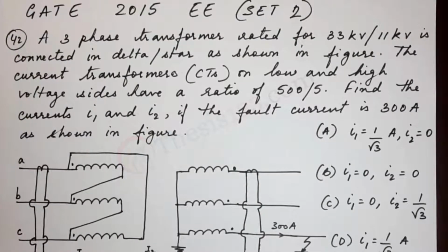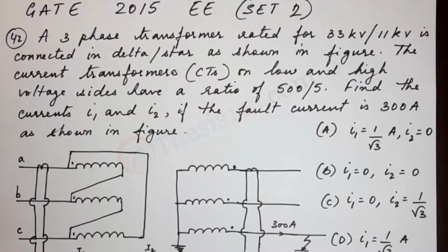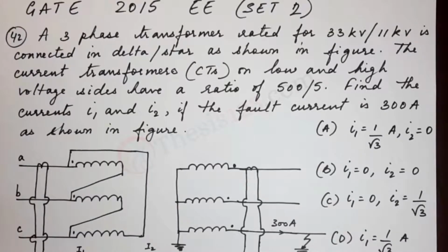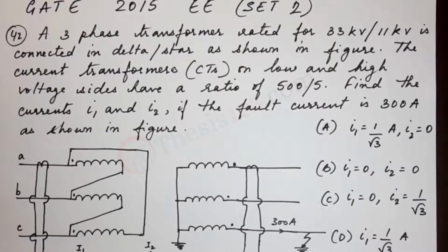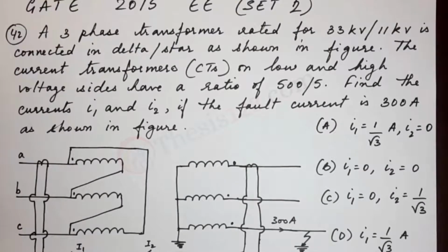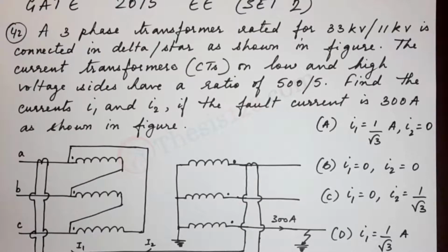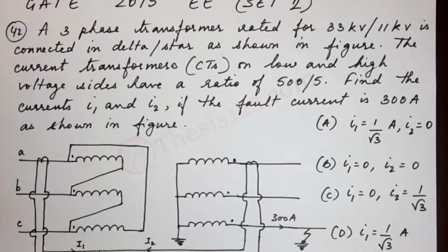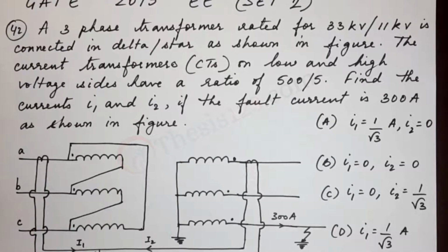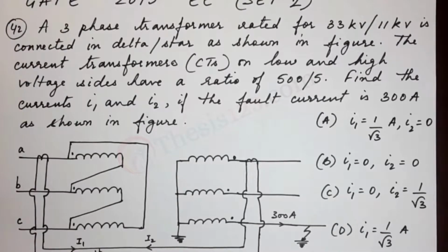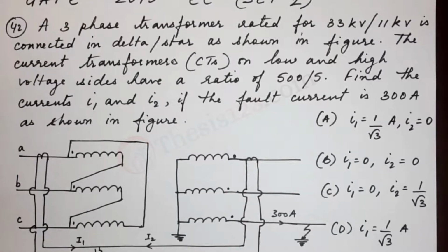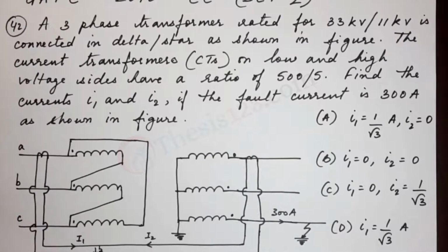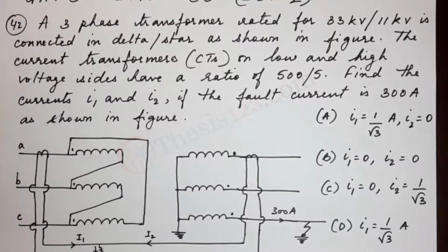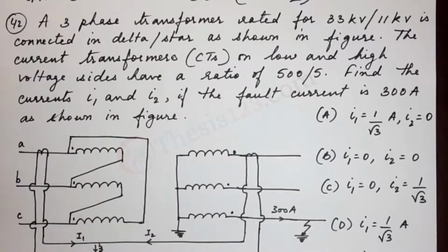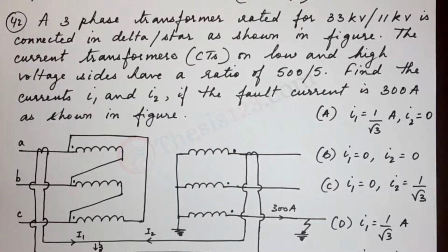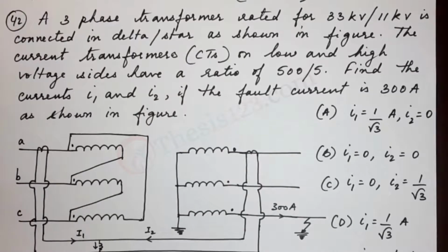Here's the next question, number 42. A three-phase transformer rated for 33 kV by 11 kV is connected in delta star as shown in the figure. The current transformers on low and high voltage sides have a ratio of 500 by 5. Find the currents I1 and I2 if the fault current is 300 amps as shown in the figure. Okay, we have our options given to us, I1 and I2 values.